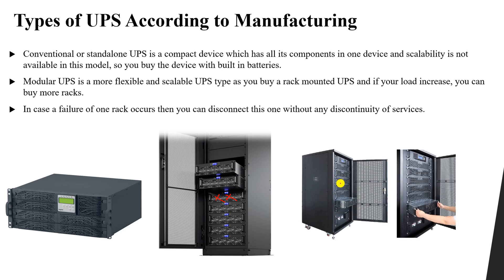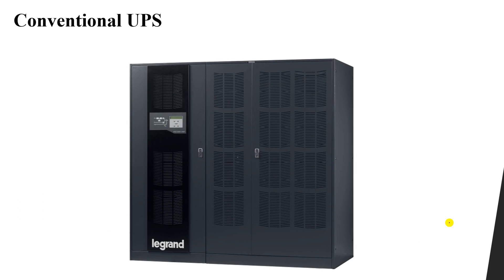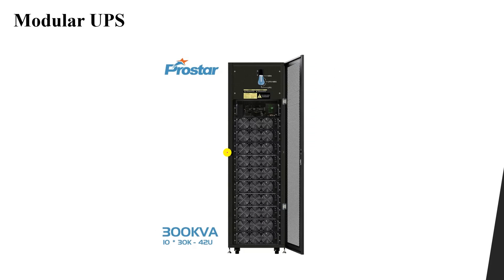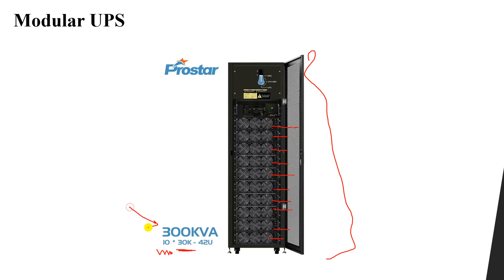As you can see, each rack contains one module that can be added or removed as needed. Here you can also see an image of the conventional UPS with all components inside it. Looking at an image of a modular UPS, we can count 10 racks or 10 modules. Each module is rated at 30 kilovolt ampere, giving a total system rating of 300 kilovolt ampere. In this lesson, we covered the conventional UPS and the modular UPS and the key differences between them.